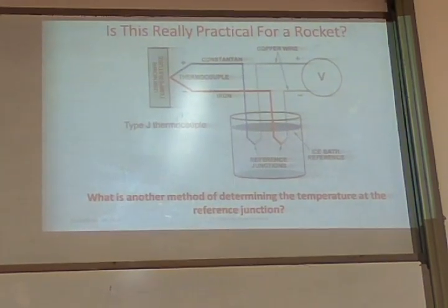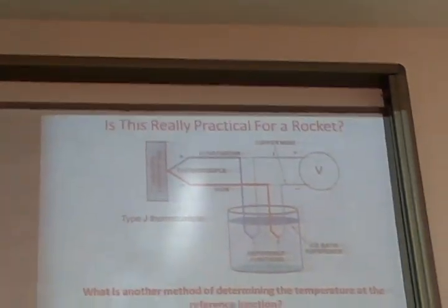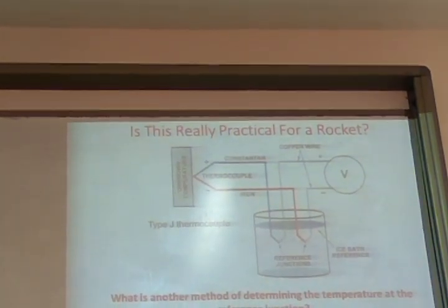Sir, any time I want to measure temperature using a thermocouple, do I have to always carry an ice bag with me? No need. You can keep it at room temperature, but we should know what the room temperature is.